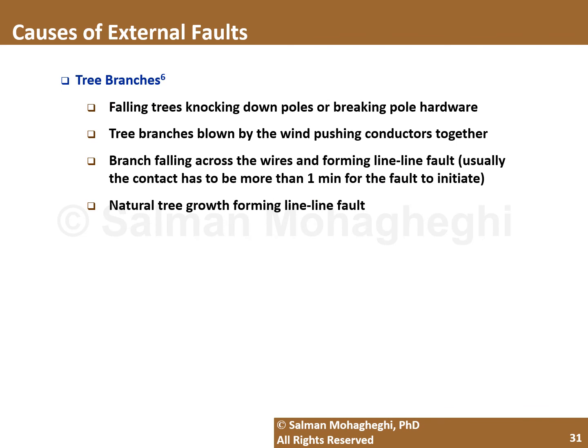The other cause of external faults would be tree branches. There's a variety of different scenarios for this. For example, you could have a relatively big tree or a tree branch that falls on a pole or on a transmission line and essentially breaks the line open. Or the lighter branches could be blown by the wind and connect the conductors together, and then you will have a line to line short circuit.